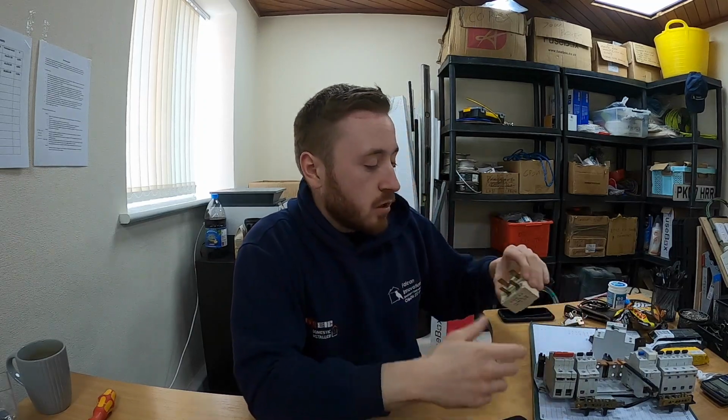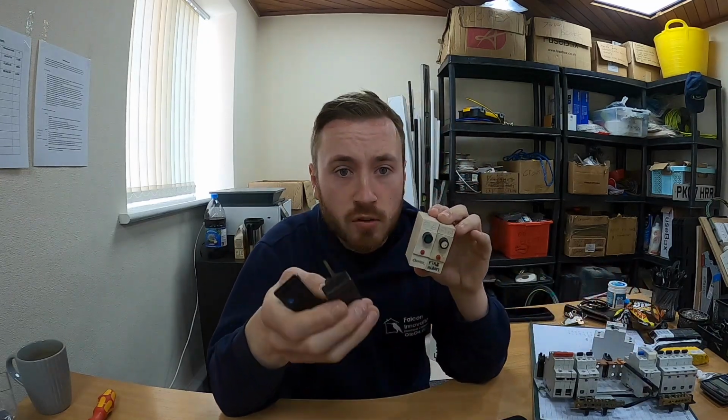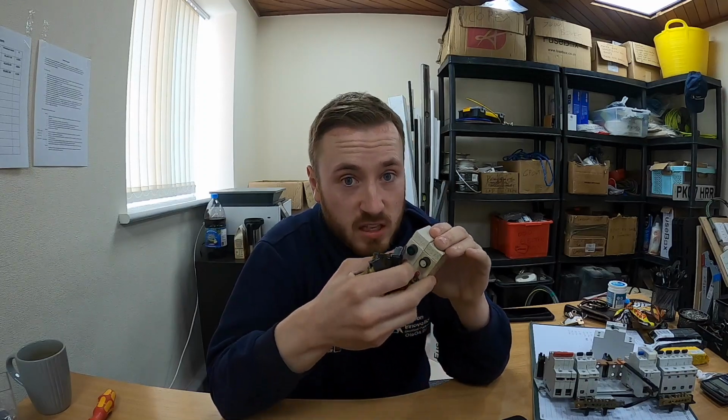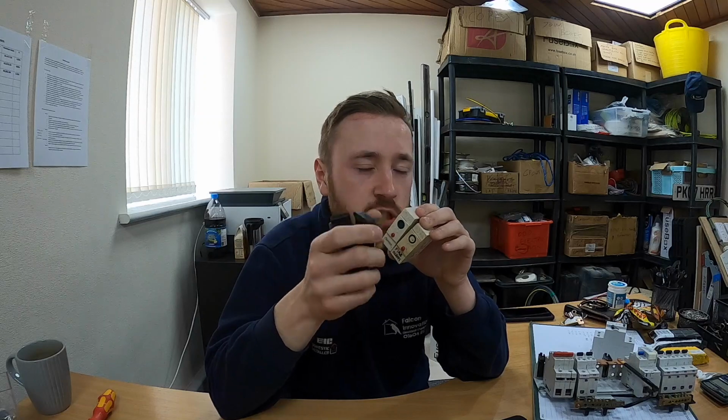Okay. Number 2 of why you may need a fuse board upgrade is you have very old circuit breakers like these. Now chances are, if you've got these, you won't have RCD protection either anyway, but if you're unsure, anything like this was 1966 to about 1983-ish.